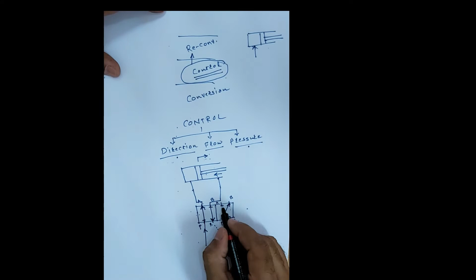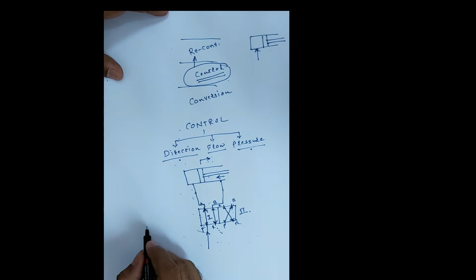So in this position, P gets connected to A. Now here are P, A and B, and here P and R. If P gets connected to B, what will happen? The flow will be to the right side of the piston, or rod end side of the piston, and the piston will retract. So P is connected to B, and at that instant A will be connected to R. That is, the return air will go through this port and be released. Mind you, these are two positions of the valve, position 1 and position 2. In position 1, P is connected to A, therefore the piston moves to the right side. In position 2, P is connected to B, therefore the piston moves to the left side. Now let us try to understand this valve symbol. The symbol is drawn like this.